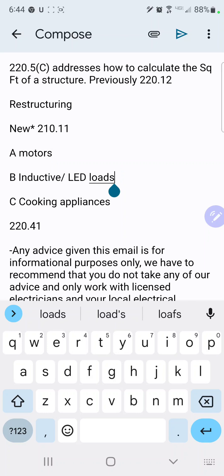I want to stop on inductive and LED lighting loads — that's Part B of this new section. It says for circuits supplying units that have ballast transformers, auto transformers, or LED drivers, it shall be calculated based on the total amperage rating of such units and not the total wattage of lamps. So if you had a 7-amp rated fixture but the total wattage only equaled 3.5 amps, you would have to use the 7 amps for the load calculation.